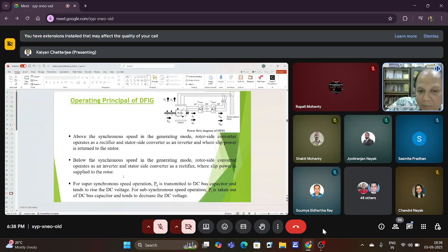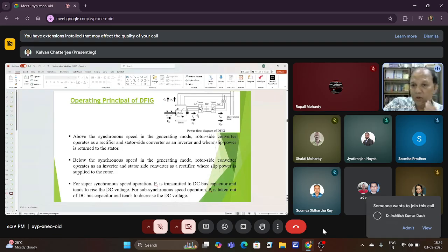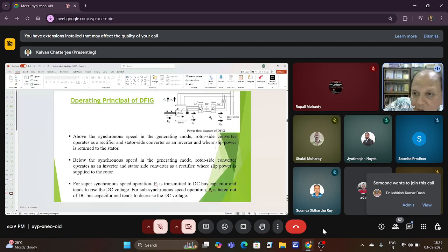When slip power is supplied to the rotor, there is bidirectional power flow through the converter. For super-synchronous speed operation, PR is transmitted to the DC bus capacitor and tends to raise the DC voltage. For sub-synchronous speed operation, PR is taken out of the DC bus capacitor and tends to decrease the DC voltage. So during normal steady state condition, PR equals PGC.